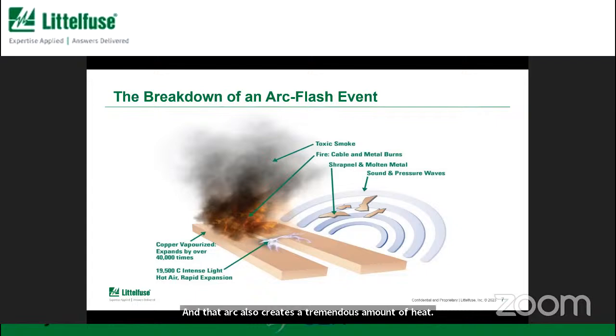The arc itself can be up to 20,000 degrees Celsius, and that extreme heat in that arc will really vaporize the copper. So it turns from a solid to a gas and expands in volume. As it expands in volume, it pressurizes the compartment, and then that can cause the blast of the enclosure, and then all of that heat and the toxic gas and everything can come out and affect somebody who could be standing by.